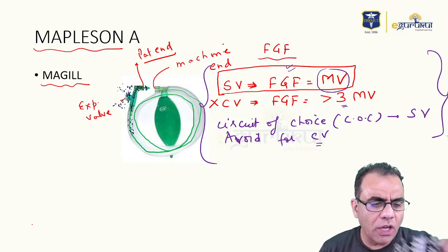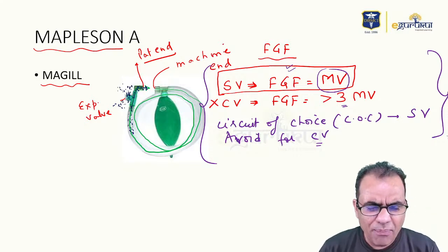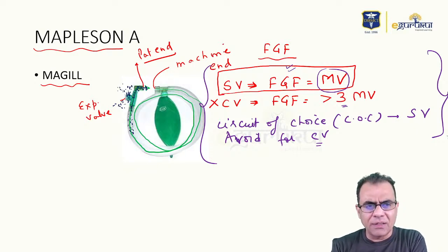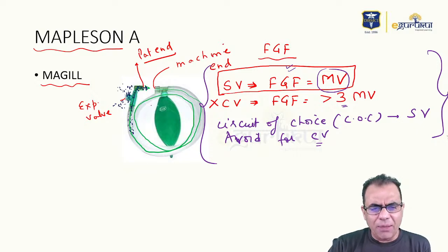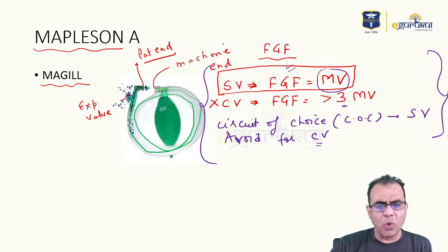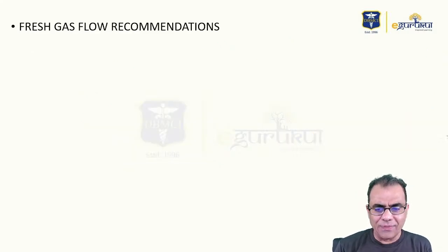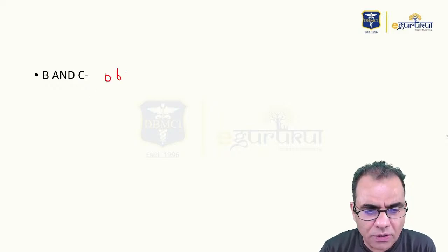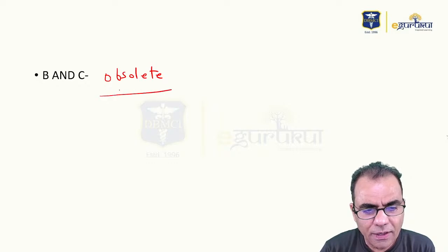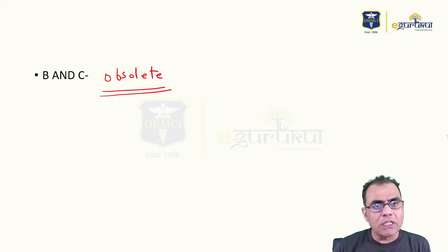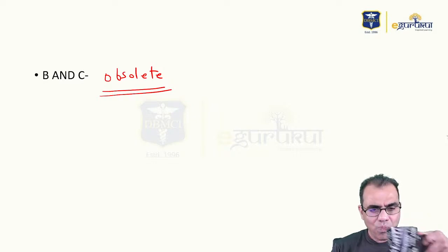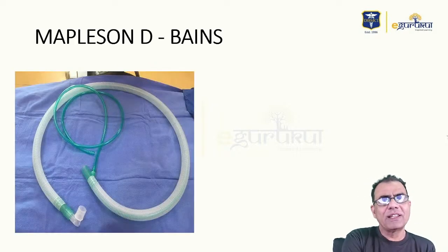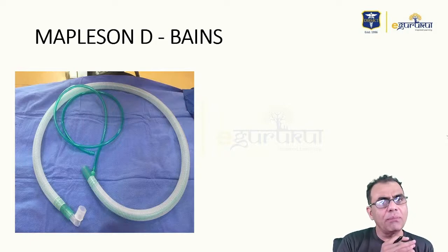So initially, Mapleson was making some changes to the Magill circuit. Like in type B, he brought this expiratory valve from here to here. So that became a disadvantage, and the circuit became obsolete. In type C, he reduced the length of the tubing. So the circuit again became ineffective. So B and C, you can say, are obsolete, no more used. Then Mapleson D.